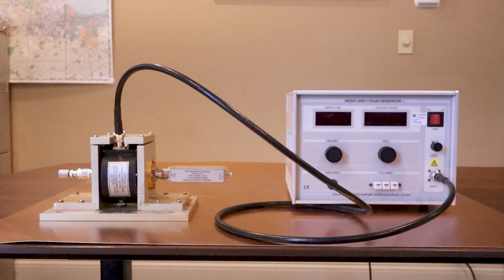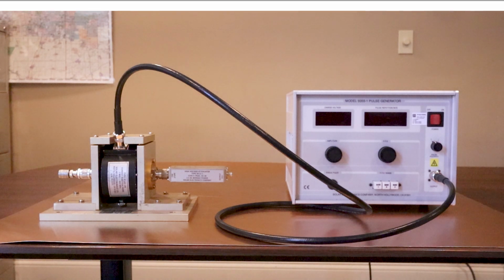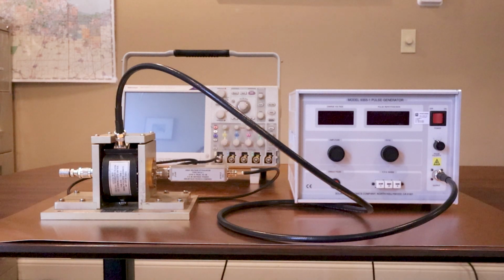Now let's go ahead and verify a waveform quickly. Alright, here's the waveform we captured through our Solar 9142-1N and the associated calibration fixture. All we did prior to capturing the waveform was to power up the transient generator and set the associated test level. Now if we look at the Solar 9355-1 manual as well as MIL-STD-461 CS115, this waveform does meet the requirements.